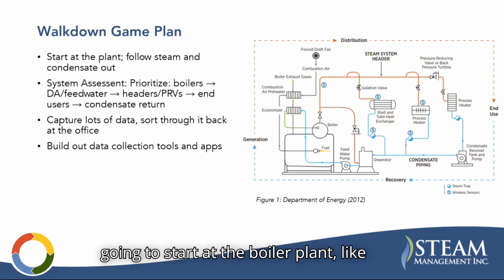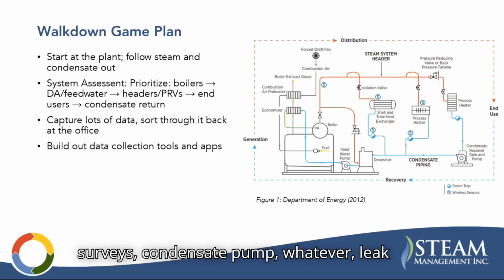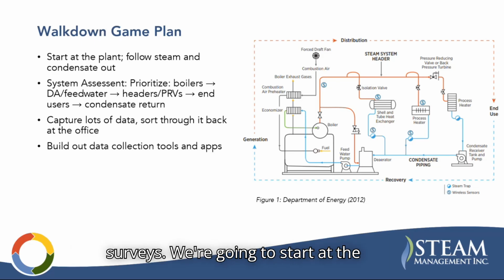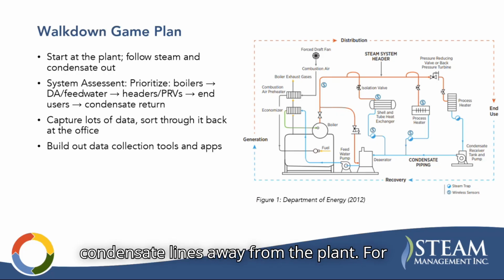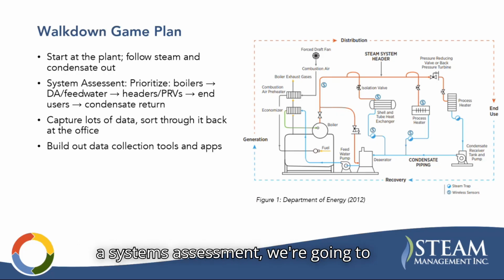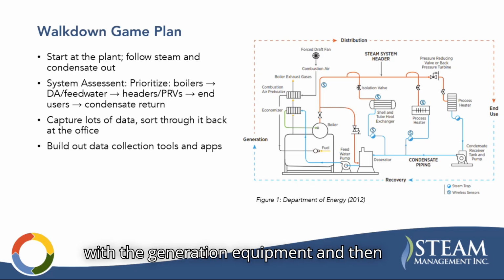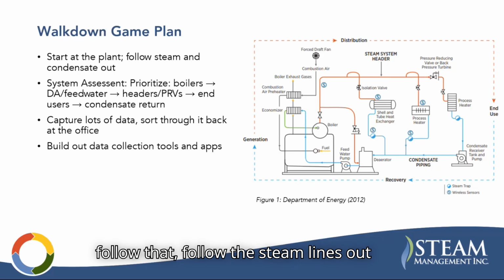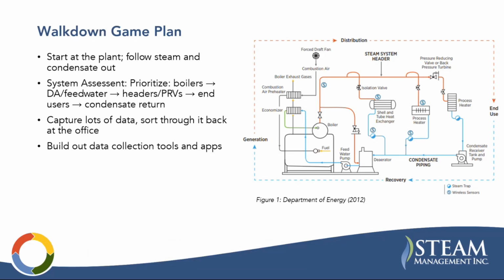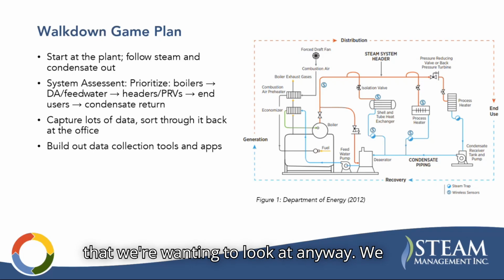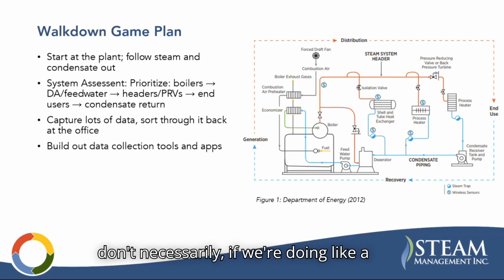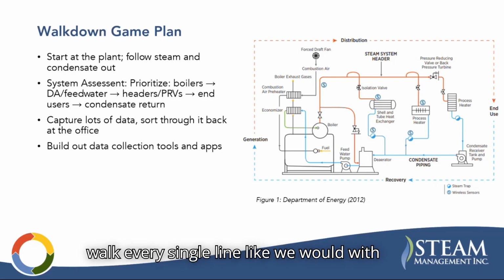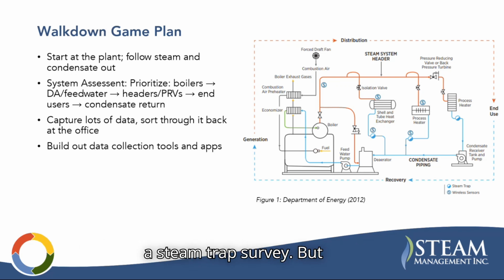For most surveys, we're going to start at the boiler plant, so steam trap surveys or installation surveys, condensate pump, whatever, leak surveys. We're going to start at the boiler plant and follow the steam and condensate lines away from the plant. For a systems assessment, we're going to spend a lot of time in the boiler plant with the generation equipment, and then follow the steam lines out to the end users that we're wanting to look at anyway. If we're doing a system assessment, we don't necessarily walk every single line like we would with a steam trap survey.